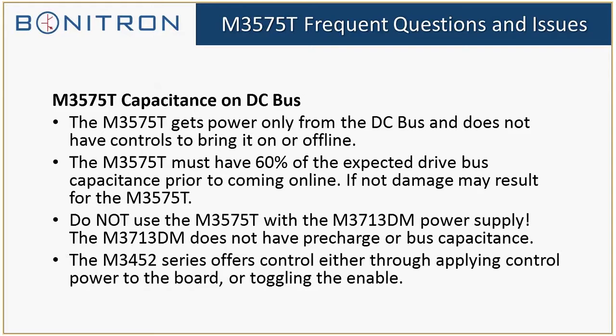You cannot bring the 3575T on and offline, just depending upon the capacitance. For those, I really do recommend using the 3452, where you can either control whether it's enabled either through toggling the enable input or just controlling power to the control board. It's not ideal to bring the 3452 on or offline with the control power because it takes some time to get up and running, about 4 to 7 seconds depending on the unit. But it is a better solution than having the M3575T, and you're trying to bring drives on or offline.